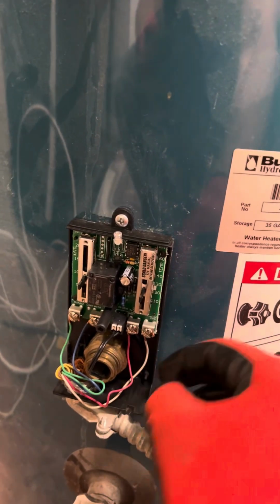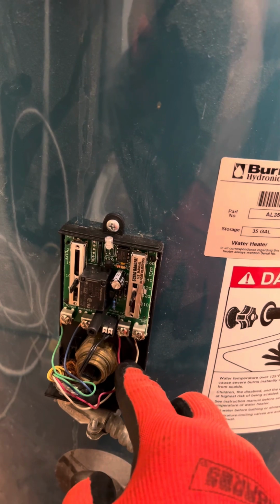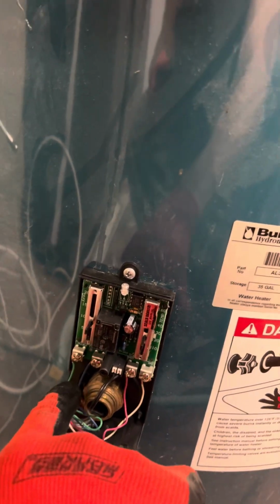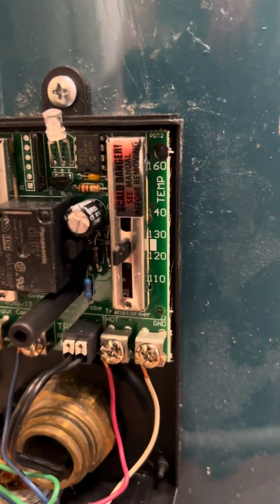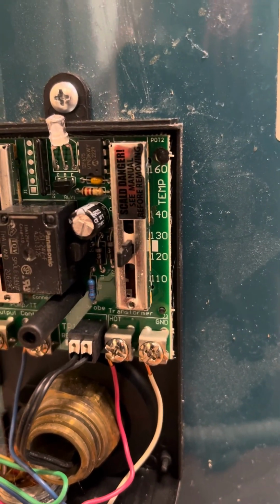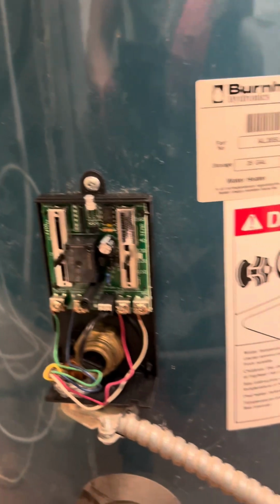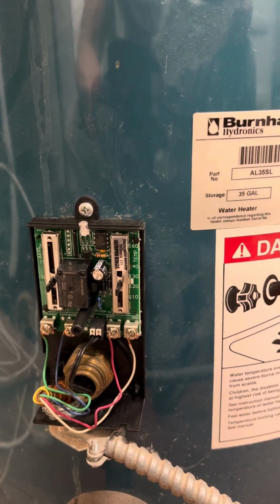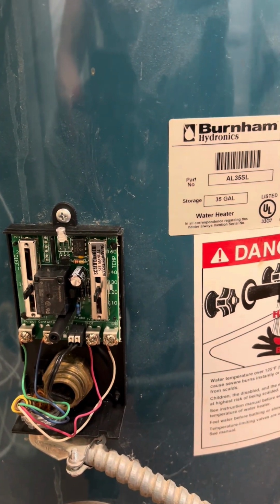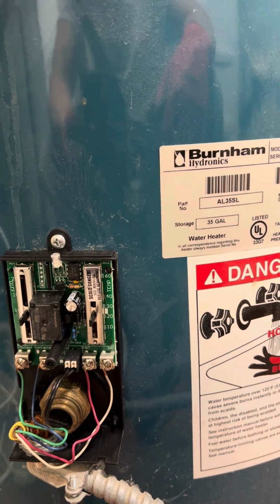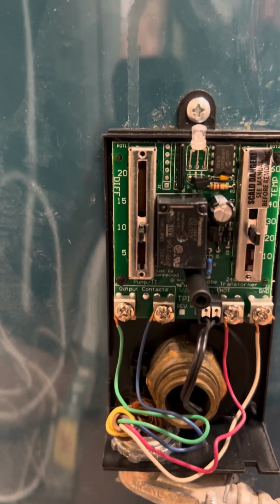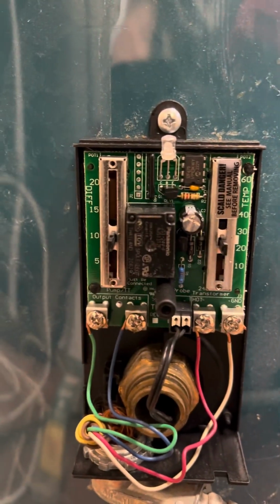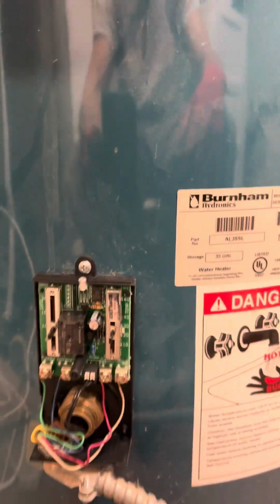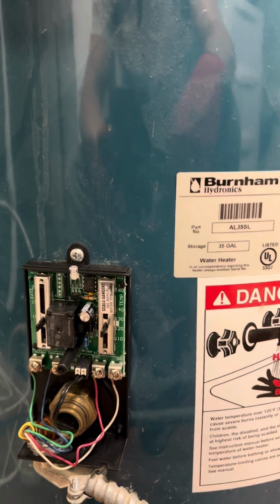Here's the 24 volts, and here is the switch for the Aquastat. Now if you notice down here, right around 125, that's a good water temperature for hot water, especially if you have kids in the house, because you don't want them to just put the hot on and get scalding hot water out. This is the differential. So around a 10-degree differential. You got 125. When it gets down around 115 or 110, it's going to kick back on. Okay, so it's going to shut off at 125.